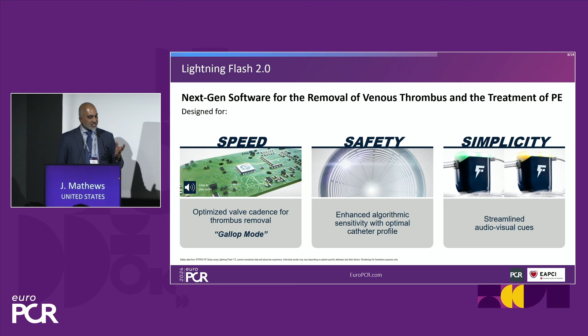So this is 1.0 versus 2.0. In the past with 1.0, there was a sampling mode, and there was a clicking that you would get to tell that you were within clot. Then if there was occlusive thrombus within the catheter, it would go into this flash mode where you have a rapid cycling of the pressure and also increased blood loss. They were able to simplify this down to the sampling mode and gallop mode. So now you just have a system where if it's flashing green, you're in an open vessel.